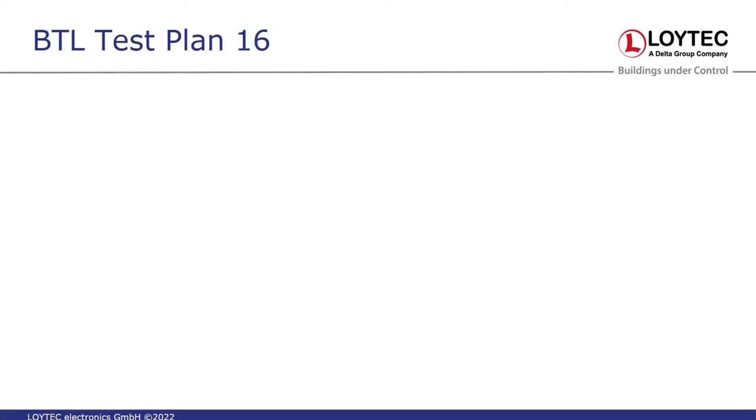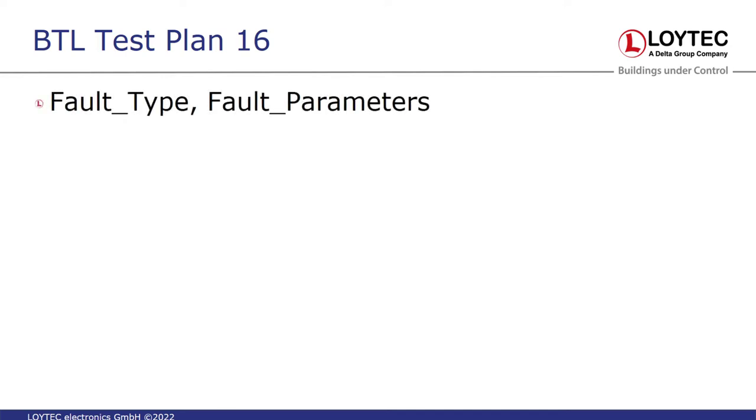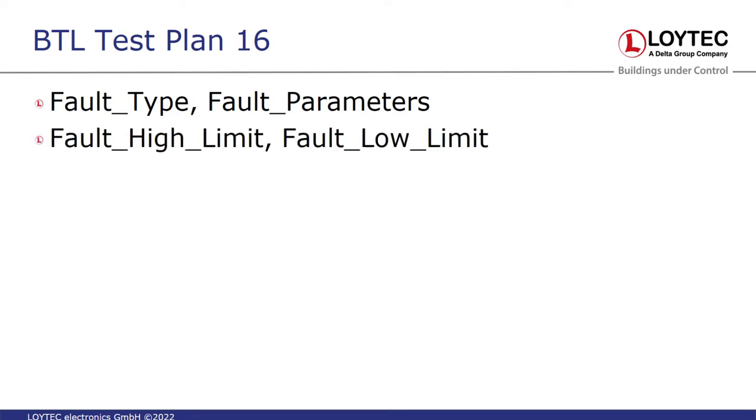All LOYTEC BACnet models have been updated and now comply with BTL Test Plan number 16. New BACnet features have also been added. There is now support for fault type and fault parameters in the event enrollment object. Fault high limit and fault low limit properties are also new. Also, there is now support for extended jumbo MSTP frames.